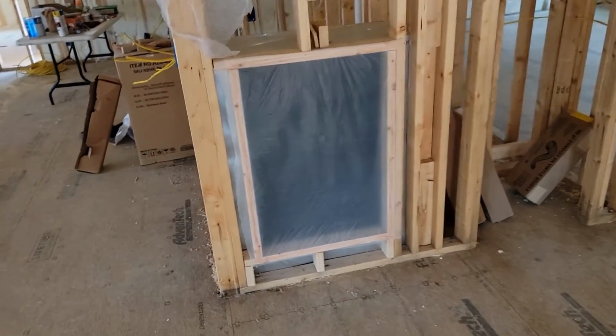So we've got about 800 square inches, which is 4 tons. We're installing a 5-ton unit. It's got about 2,000 CFM in air quantity, and I'm going to have 20 6-inch vents. So I calculate one 6-inch vent for about 100 CFM. So that's going to be perfect for this 5-ton unit.